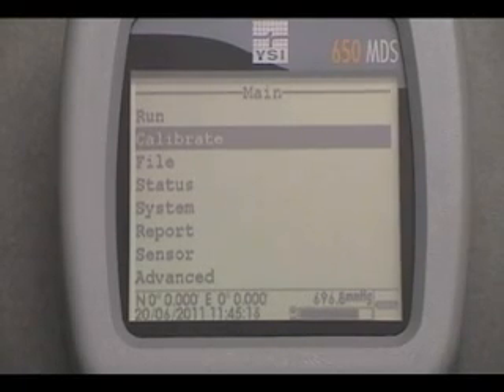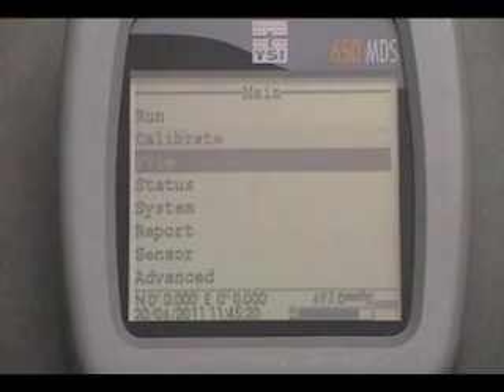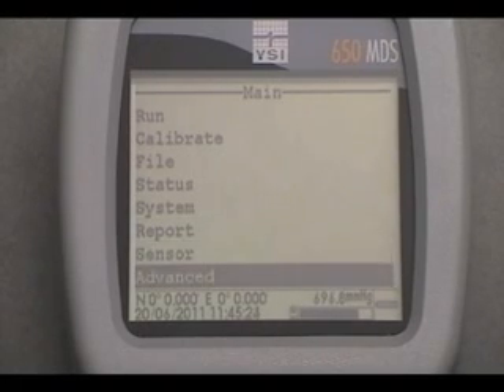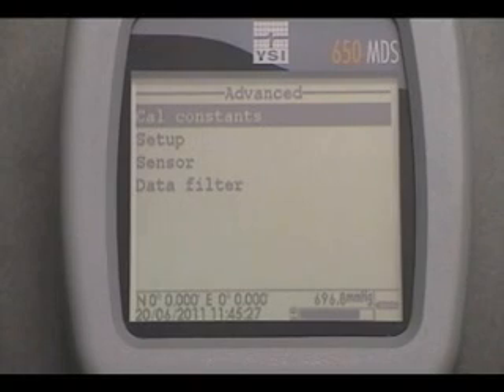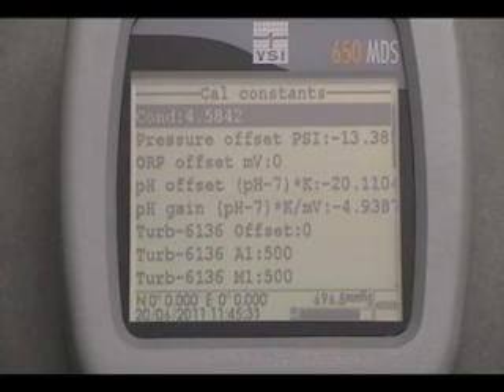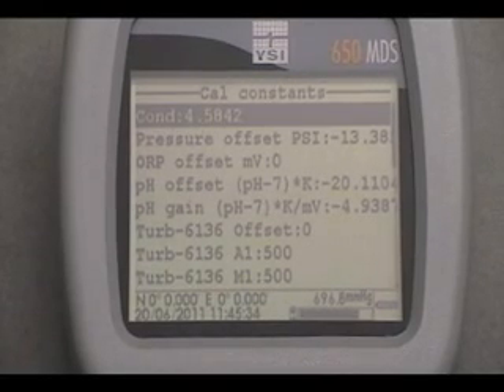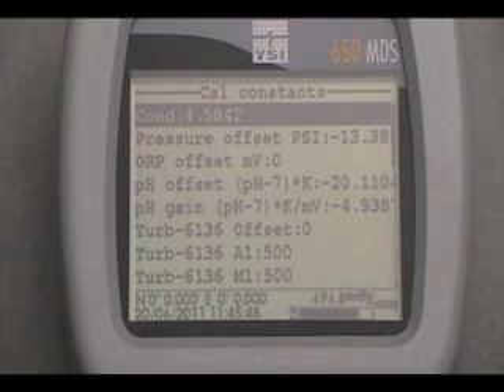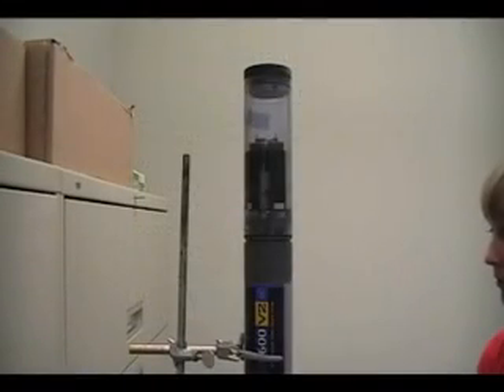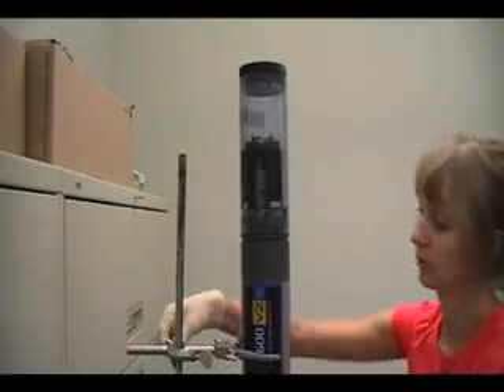Look for the conductivity cal constant under Advanced, Enter, Cal constants, Enter. The conductivity cal constant should fall between 4.55 and 5.45 and should not vary from the historical value more than 0.1. You can look back at previous calibration sheets to determine the historical value. If the value doesn't meet these criteria, the calibration standard may be off. You can try another bottle of calibration standard. If the constant is still off, it's best not to deploy this sensor and contact ENR for support. Step 13. Turn the sonde back to its normal orientation.